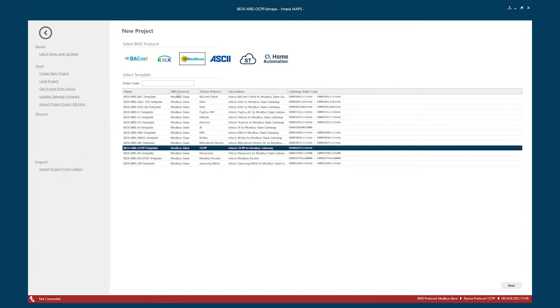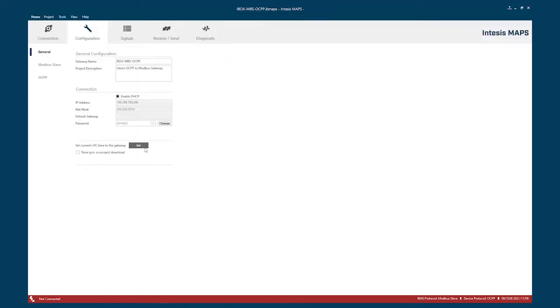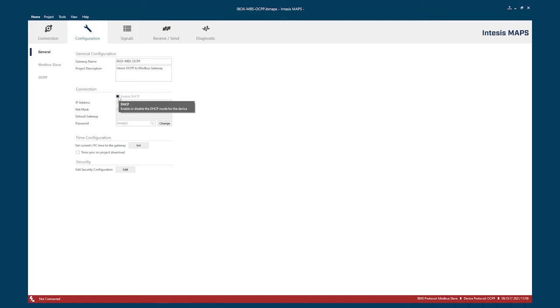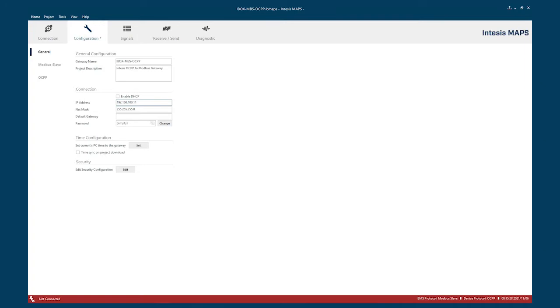So let's begin. We are here in Maps. You will find the template for the Modbus to OCPP. Just open this app. It will take you to the general configuration. It comes by default with DHCP. You can just choose the settings that adjust to your installation. In my case, I'm going to put this gateway in 192.168.1.119. Just have in mind that your charger will need to be within the network.